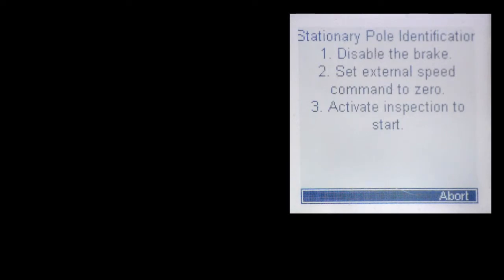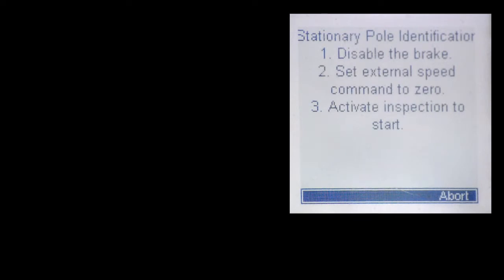Secondly, for any analog and serial speed control, the inspection speed needs to be set to zero. Since the drive will clamp the speed command at zero, this will ensure that the controller does not fault on a speed deviation error.